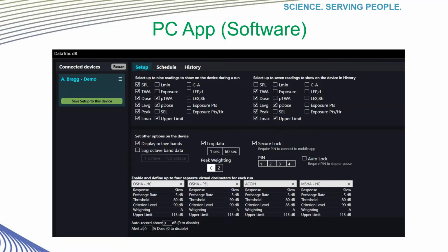There are now 3 tabs in the software: Setup, Schedule, and History. The screen you see here, as I mentioned earlier, is Setup. This screen is where you can set up what you want to see on the device and how you want the device to measure. You can select up to 9 readings to show on the device. We will probably be choosing a standard setup for the units when they leave SKC. If you notice the boxes that are already checked, these will most likely be the way it is sent out.